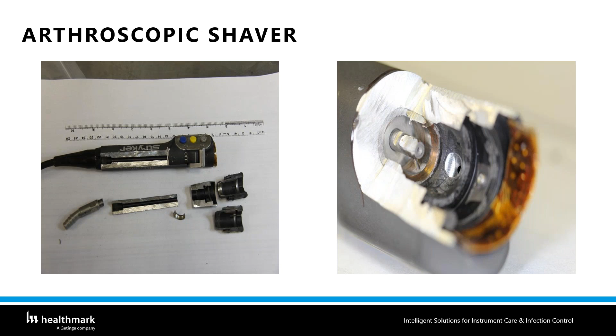But just make sure the IFU says that you need to look inside it, because these are kind of difficult, at some point I'd say impossible, to clean, because you have all these nooks and crannies. Then I was looking at one of them, I think it was ConMed, and they say to use a brush. They don't say, for example, what size of brush you need to use. If you look at this, you see there are different sizes here; one probably needs a huge brush, and as you go down, you need a smaller brush.